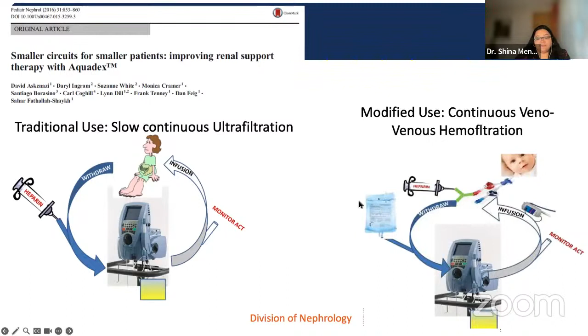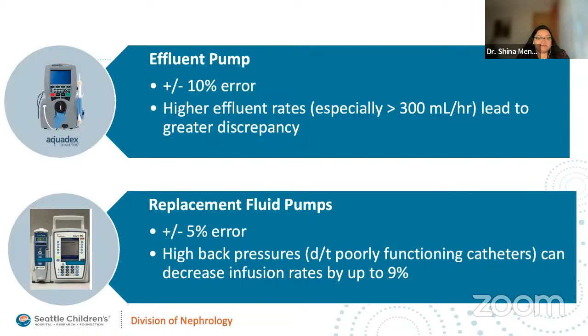Now, the thing is, the device is not meant to provide dialysis or convective clearance. So this step here of the replacement fluid requires a separate infusion pump, and these do not communicate with each other. So that can sometimes be a little bit challenging, in the sense that if one machine stops, you have to be very cognizant of the other machine and make sure that it is also stopped. And then they both have their own errors, which can add up to a significant fluid discrepancy in a small neonate.